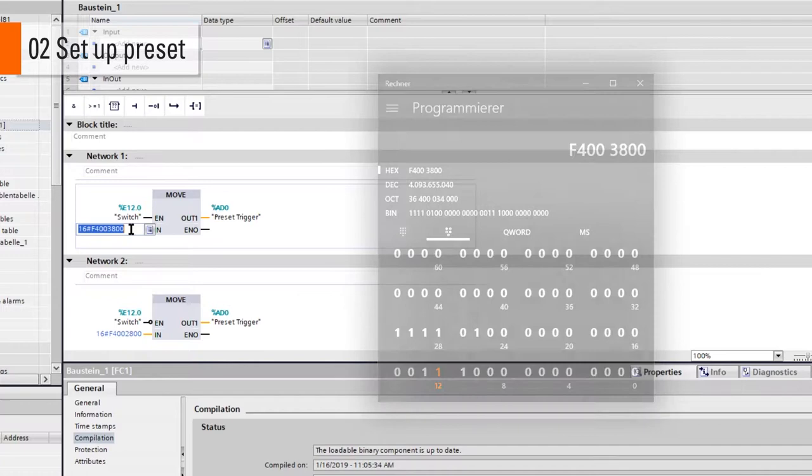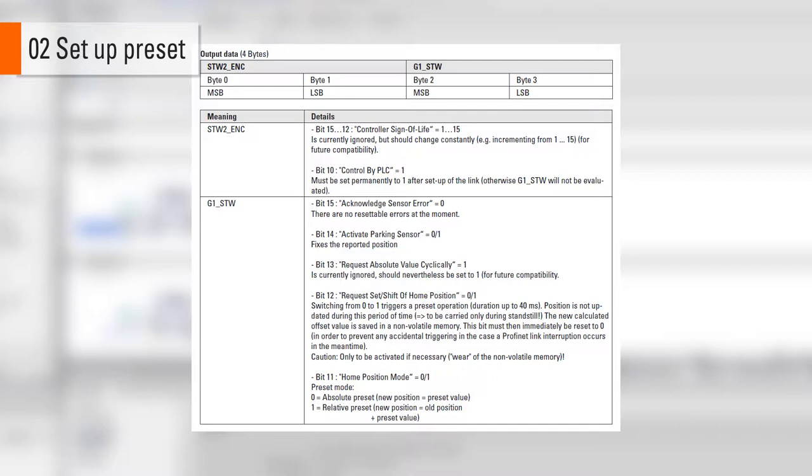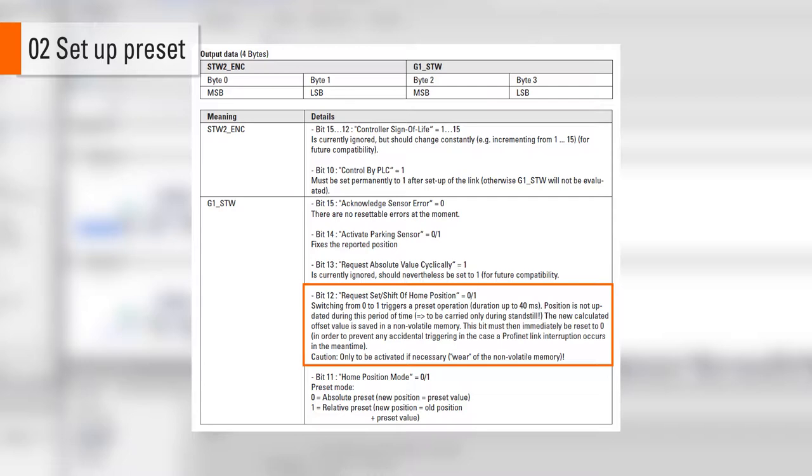To understand why exactly this hex value is needed, we have to take a look at the structure of the telegram. Here we can see that the G1 STW is a 16-bit value which contains Request Set/Shift of Home Position, the bit 12, and the home position mode, the bit 11. If bit 12 shifts from 0 to 1, the preset is triggered.